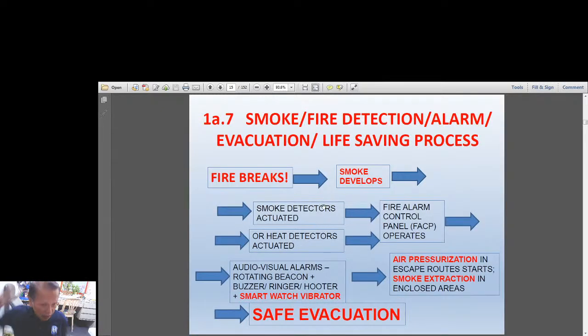So now here, let's analyze two slides which would explain the sequence of operation of a fire. I mentioned this first slide as the life-saving process: smoke, fire detection, alarm, evacuation, life-saving process. So when a fire breaks out, smoke develops, and the smoke will be received by smoke detectors, and the detectors will actuate the fire alarm control panel. Or if extraordinary heat is detected by heat detectors, they will also send a signal to your fire alarm control panel, and your FACP will send a signal to your audiovisual alarm.